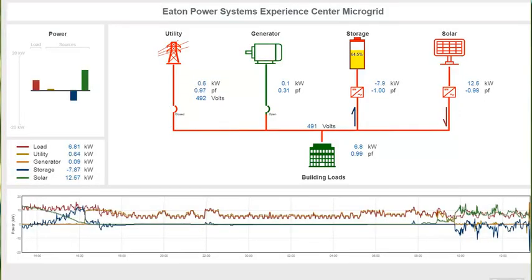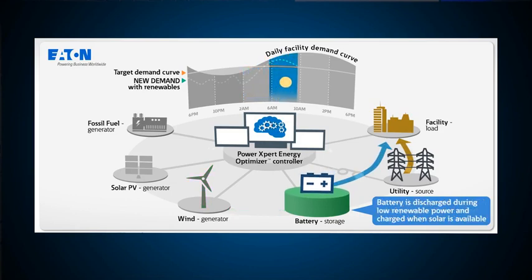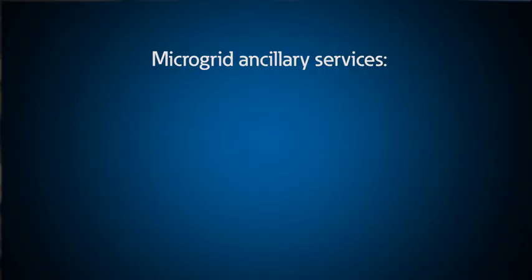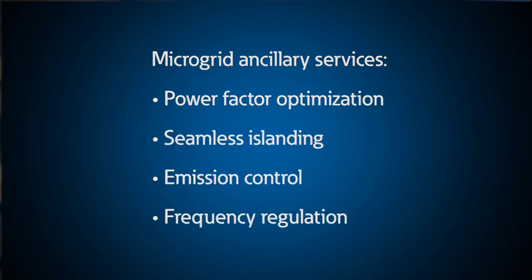This microgrid has four sources and supplies power to four large HVAC units, lights, and auxiliary loads. The four sources include the utility, a 100 kilowatt generator, lithium-ion batteries, and solar power. The microgrid seamlessly controls and optimizes the power flow from all four sources, and using Eaton's Power Xpert Energy Optimizer controller, it can optimize the system based on reliability or cost as appropriate. Additional features include power factor optimization, seamless islanding, emission control, and frequency regulation or active power dispatch for specific utility markets.